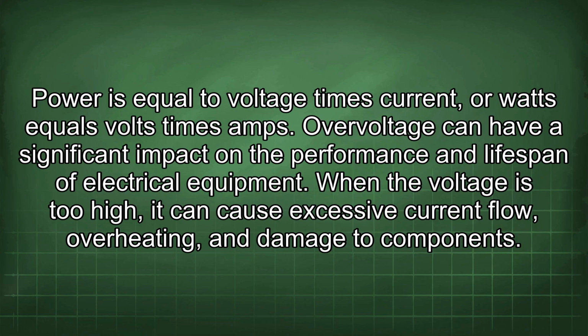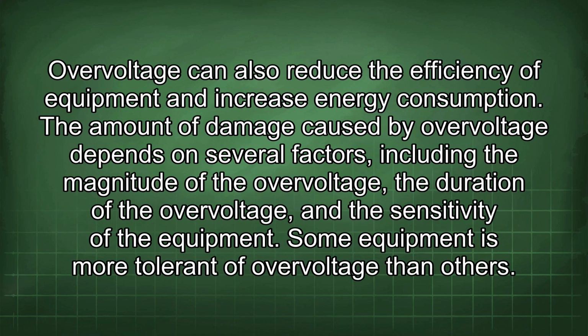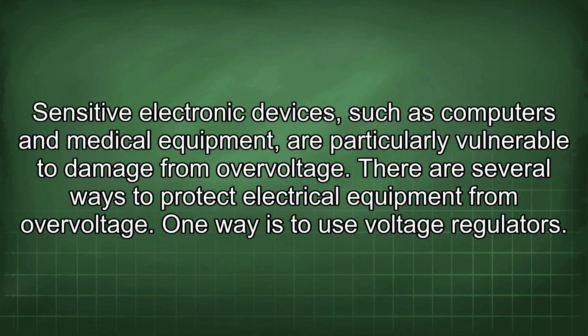Overvoltage can have a significant impact on the performance and lifespan of electrical equipment. When the voltage is too high, it can cause excessive current flow, overheating, and damage to components. Overvoltage can also reduce the efficiency of equipment and increase energy consumption. The amount of damage caused by overvoltage depends on several factors, including the magnitude of the overvoltage, the duration of the overvoltage, and the sensitivity of the equipment. Some equipment is more tolerant of overvoltage than others. Sensitive electronic devices, such as computers and medical equipment, are particularly vulnerable to damage from overvoltage.